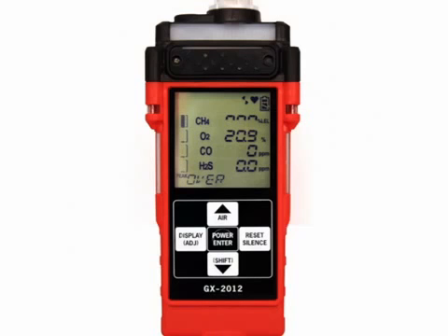Reset the alarm using the Reset Silence button once the alarm condition has cleared. Calibrate the GX2012 as described in the calibration section of the manual. If the overrange condition continues, you may need to replace the sensor that has triggered the overrange alarm. If the overrange condition continues after you have replaced the sensor, contact RKI Instruments for further instructions.